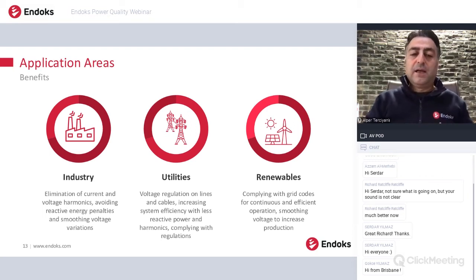On utilities, the voltage regulation on the lines and the cables is very important, which will increase the system efficiency with less reactive power and harmonics, and of course combined with regulations like EN 50160. On the other hand, for renewables, the application areas are combined with grid codes for continuous and efficient operation, and also smoothing voltage to increase the production is important. In many renewable power plants, especially in our country nowadays, for solar power plants, because of overvoltage problems, some of the solar power plants cannot operate during the day.